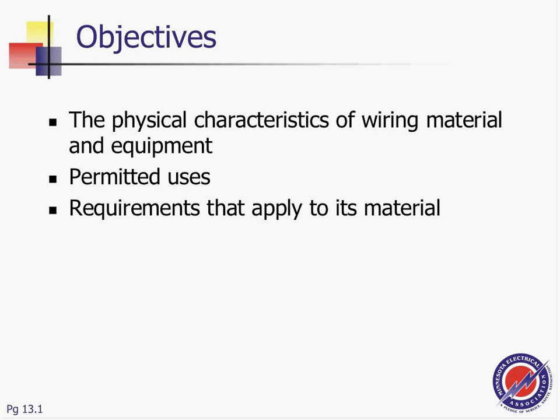So I know a lot of you guys, if you're in a commercial building, EMT it and MC it. A lot of people can solve 99% of their problems with MC cable and EMT conduit. No problem. We talked about that. This is probably your conduit of choice and your cable of choice. Now, today, guys, we're going to talk about the flexible conduits, and that can work. I always think flexible conduits almost can do the work of an MC cable. A lot of stuff that you can solve with an MC cable, with the advantage that you can add as many conductors to this flexible conduit as you desire, based on the need.